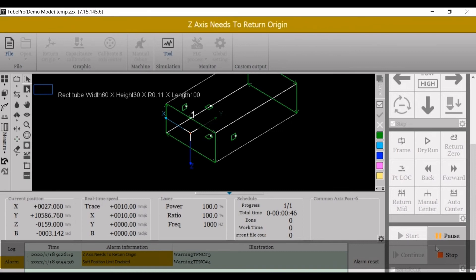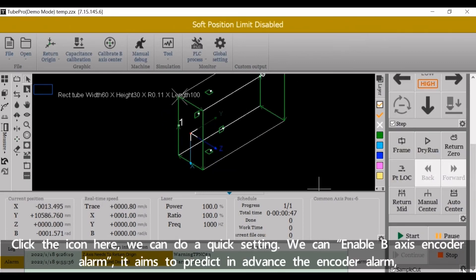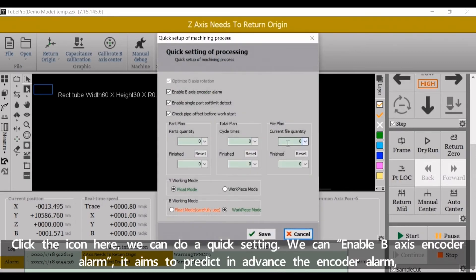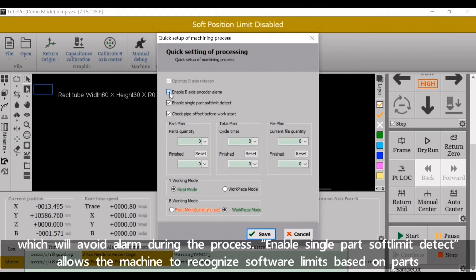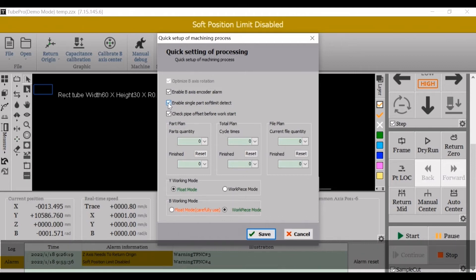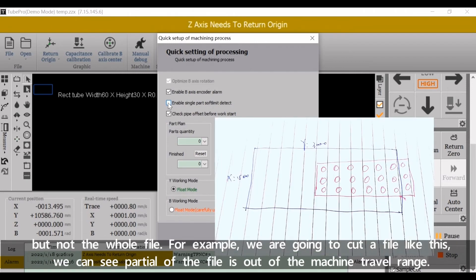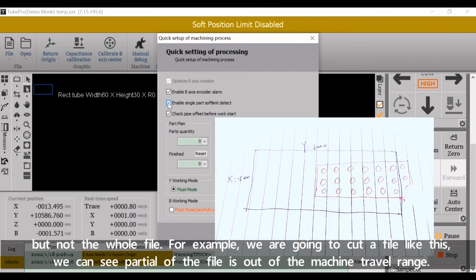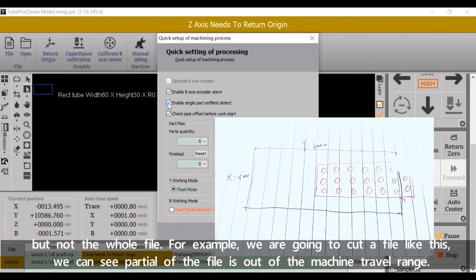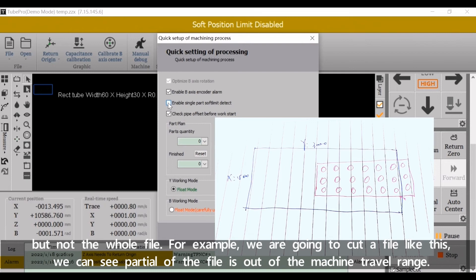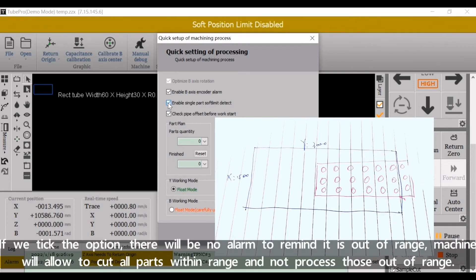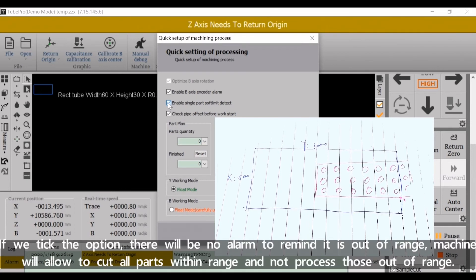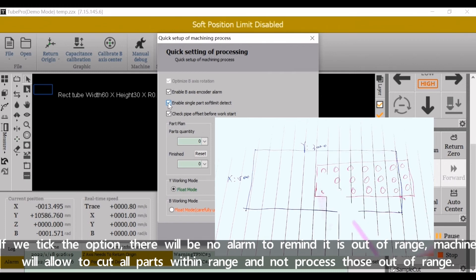Click the icon here, we can do a quick setting. We can enable B-axis encoder alarm. It aims to predict in advance the encoder alarm, which will avoid alarm during the process. If we tick the option, there will be no alarm to remind it's out-of-range. The machine will allow to cut all parts within range and not process those out-of-range.